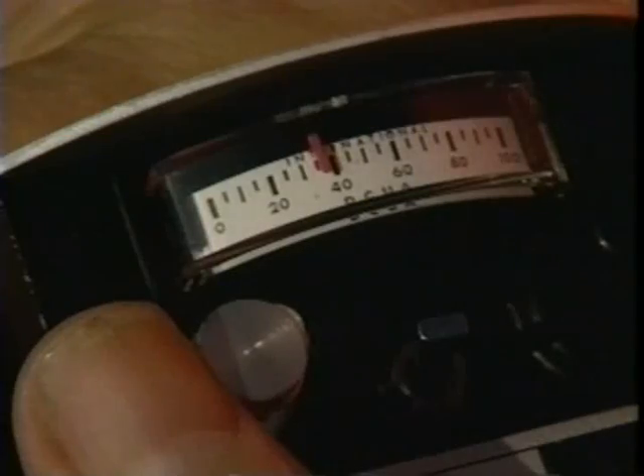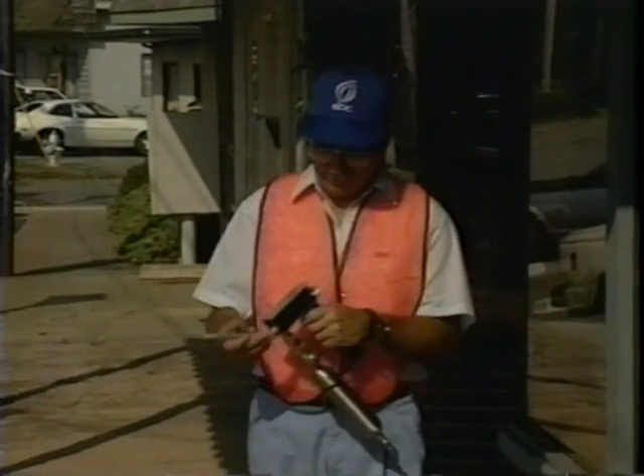The search range of the FlamePack 400 is 50 parts per million over the scale. The scale is delineated in microamps up to a high value of 100 microamps. This means that 1 part per million of organic gas is measured as 2 microamps. When the meter is maintained at 2 microamps below the alarm point, it will take only 1 part per million to cause the alarm to sound. This is the true detection sensitivity of the FlamePack 400.